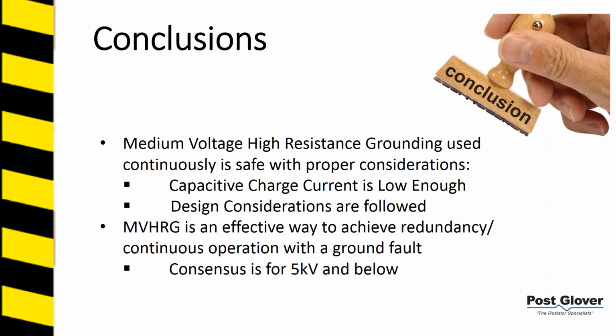You need to make sure. I would say that if you're going to do medium voltage high resistance ground, and you don't absolutely know for sure that capacitive charge current is low enough, you have to do an analysis. I think it's prudent. I wouldn't say the same thing for low voltage, but I would definitely say at medium voltage. Design considerations are followed, like talk about the over voltages, talk about the line to neutral loads. Medium voltage high resistance ground is an effective way to achieve redundancy, continuous operation with the ground fault.